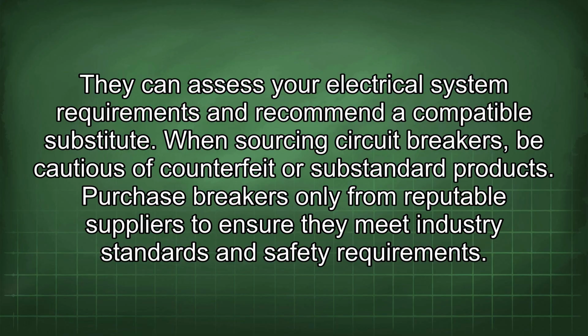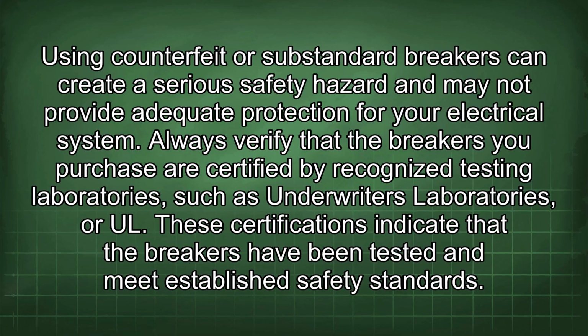When sourcing circuit breakers, be cautious of counterfeit or substandard products. Purchase breakers only from reputable suppliers to ensure they meet industry standards and safety requirements. Using counterfeit or substandard breakers can create a serious safety hazard and may not provide adequate protection for your electrical system. Always verify that the breakers you purchase are certified by recognized testing laboratories, such as Underwriters Laboratories or UL. These certifications indicate that the breakers have been tested and meet established safety standards.